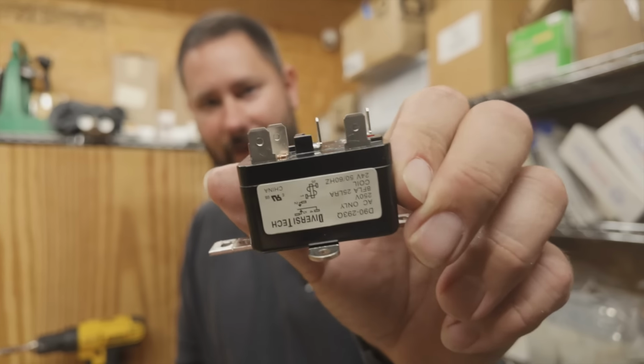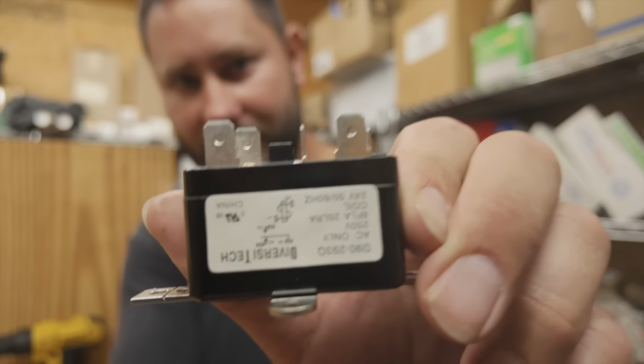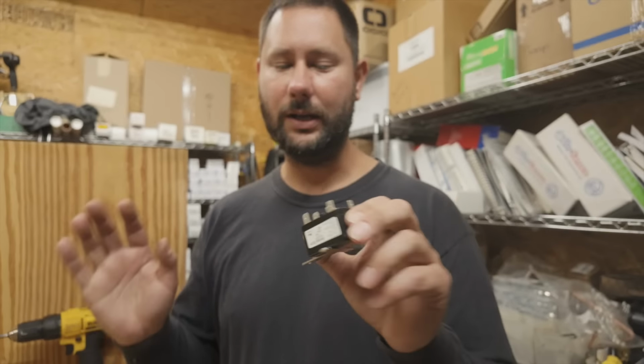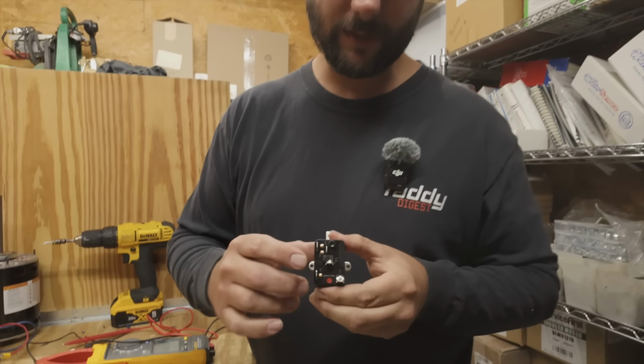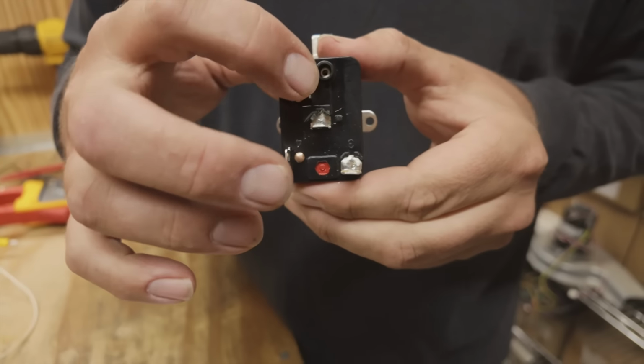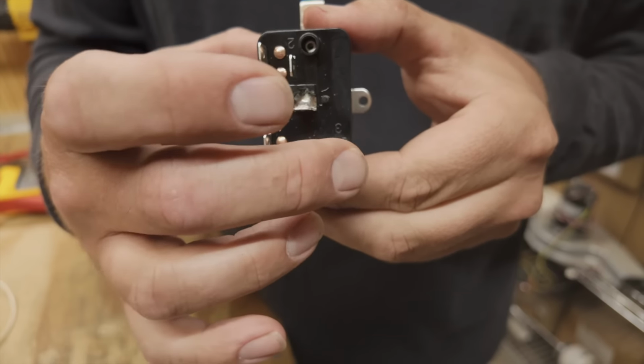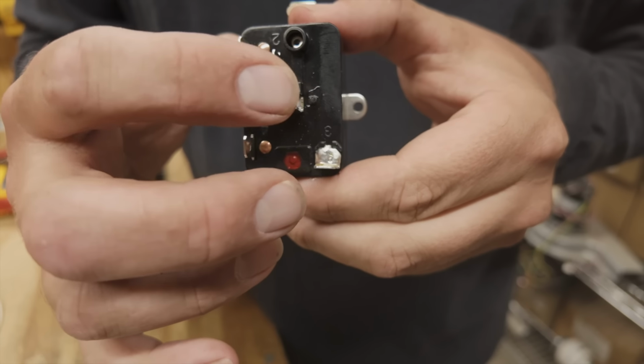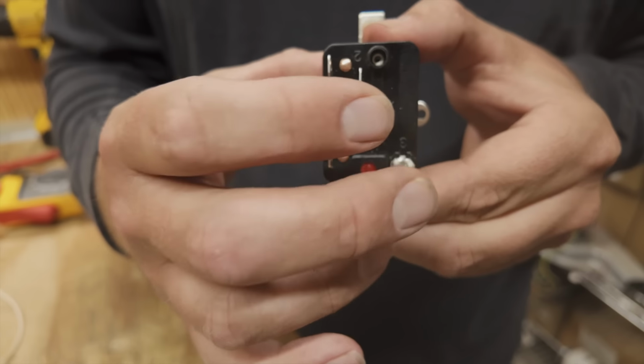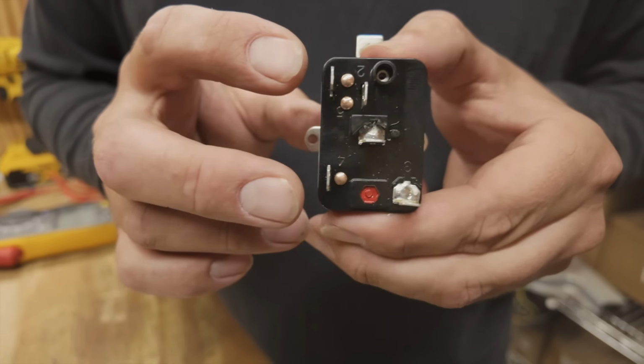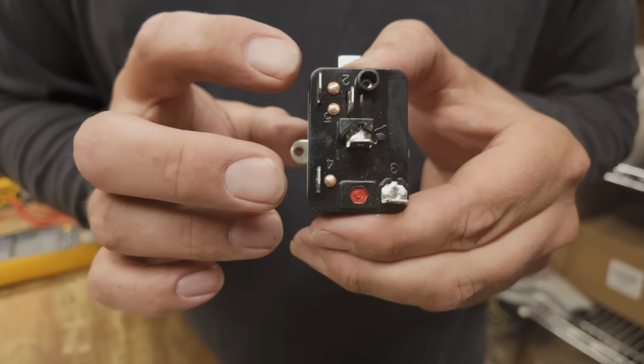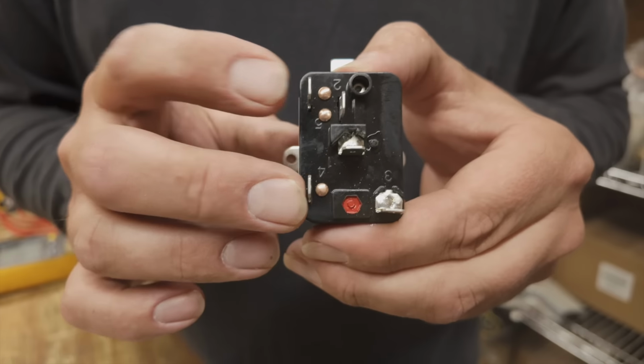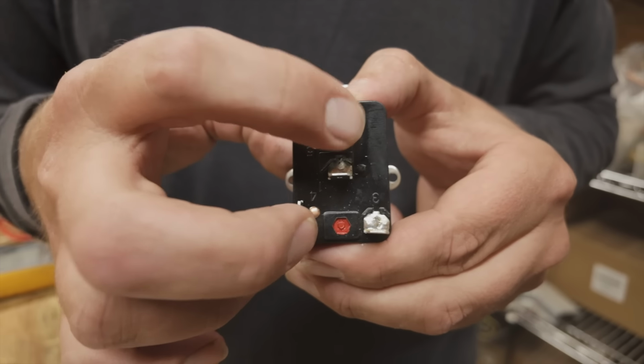Next, we have a typical fan relay. And you can actually see there's a little diagram right here, but it's kind of hard to understand. But if you look, you can see that these 3 spades look different than these 2. So between 1 and 3, we have our coil. This is where we get our 24-volt call. Between 4 and 5, we have a normally closed contact. Between 4 and 2, we have normally open.